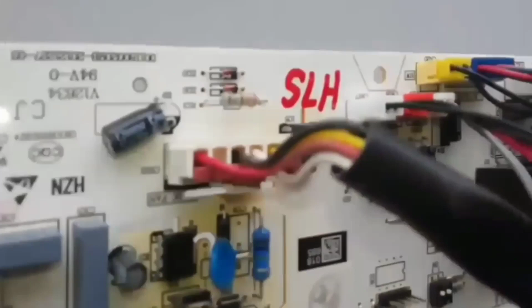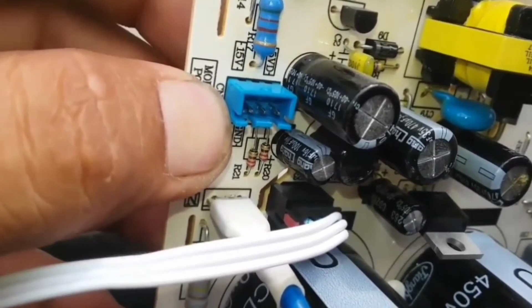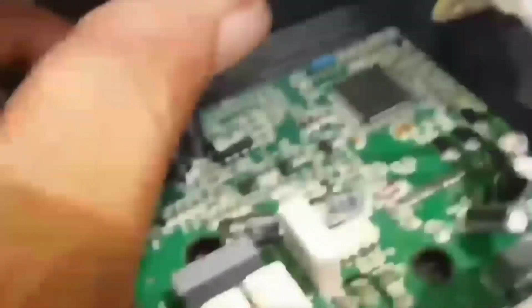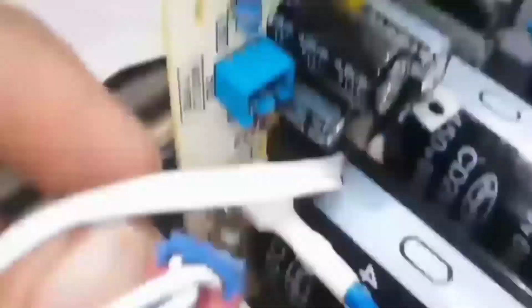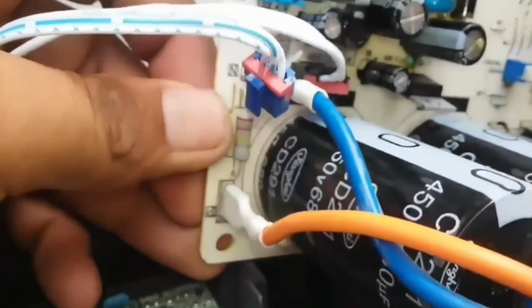Now let's check the outdoor PCB and power module. Here you can see the power module connector, which has 3 terminals. First we will check the voltage between terminals 1 and 2, then between terminals 2 and 3. On terminals 1 and 2 we should receive 5 volts DC, and on terminals 2 and 3 we should receive 15 volts DC. If we are receiving 5 volt DC and 15 volt DC, it means our outdoor PCB is okay.